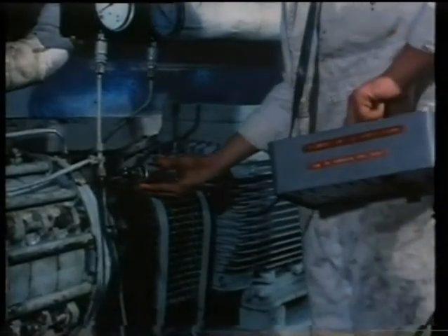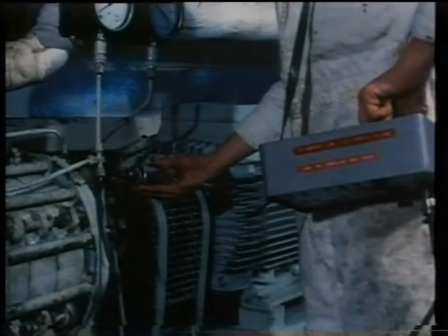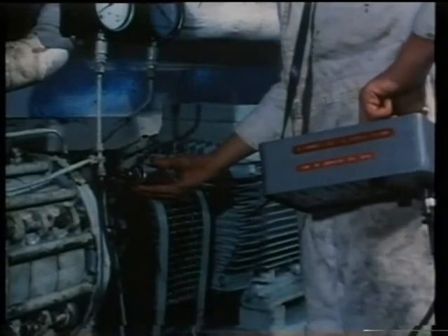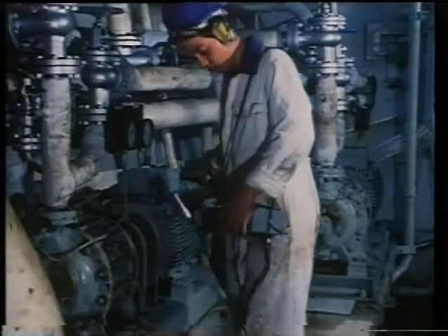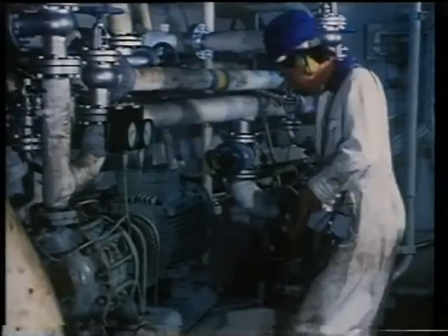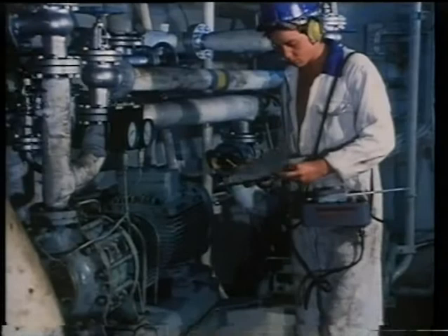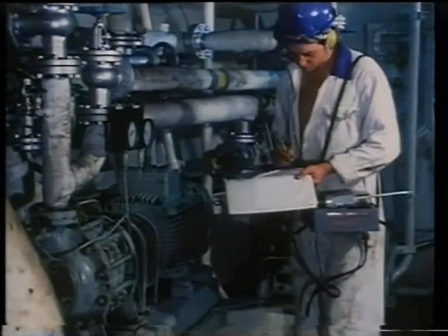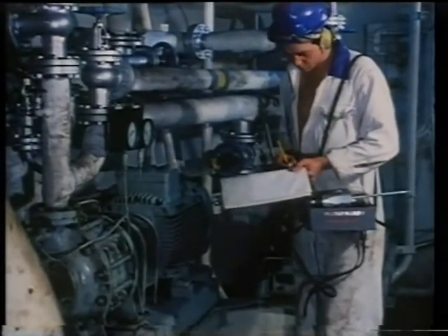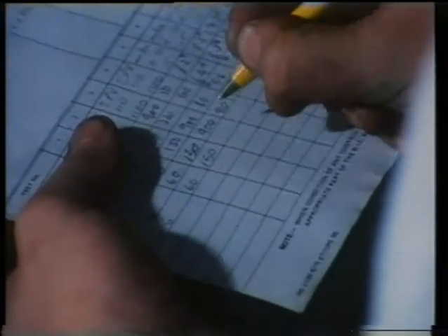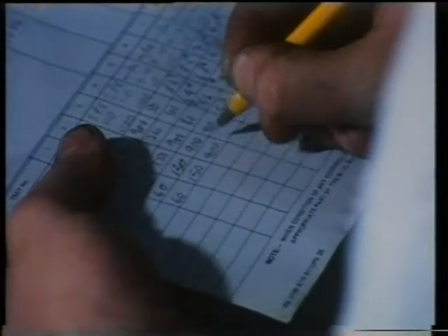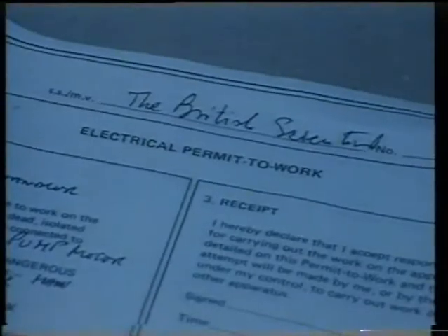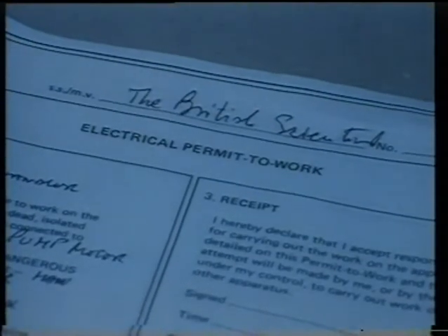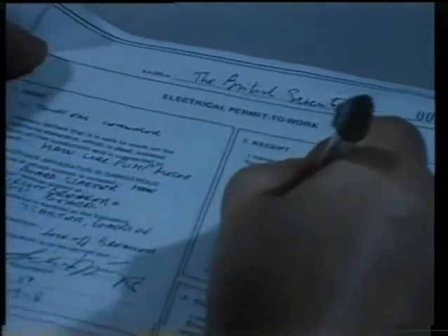Regular vibration monitoring is carried out by one or another method, seen here being done on a small pump motor. The results of the measurements are carefully recorded for future comparison. This should ensure that developing problems are dealt with before they become serious and costly to remedy. Maintenance should always be carried out on the basis of a prepared job sheet, and in the case of high voltage systems, on an approved and recognized permit to work system, which should be rigidly adhered to.